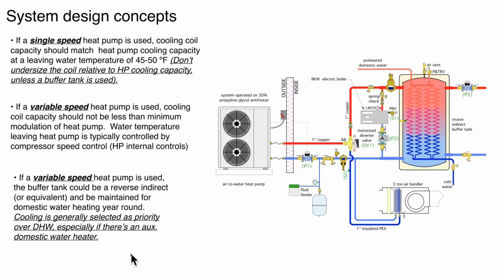I put down here, cooling is generally selected as priority over domestic hot water, especially if there's an auxiliary domestic water heater. So if we had, let's say, a 30-gallon tank as our booster, based on using these coils as a preheat, that tank could provide domestic hot water on its own, it can cover the domestic hot water load. For example, if somebody's taking a shower while the building is being cooled. So in those circumstances, cooling could be selected as the priority load.